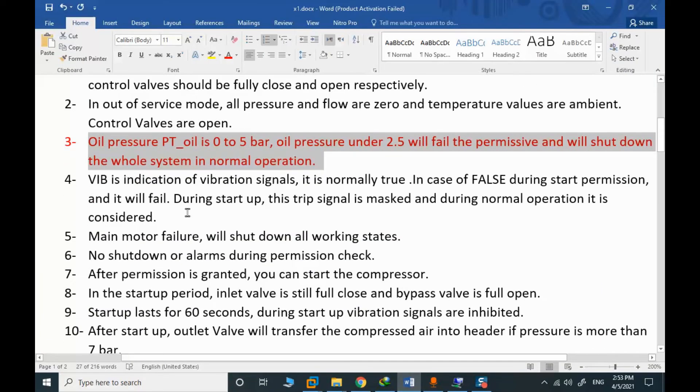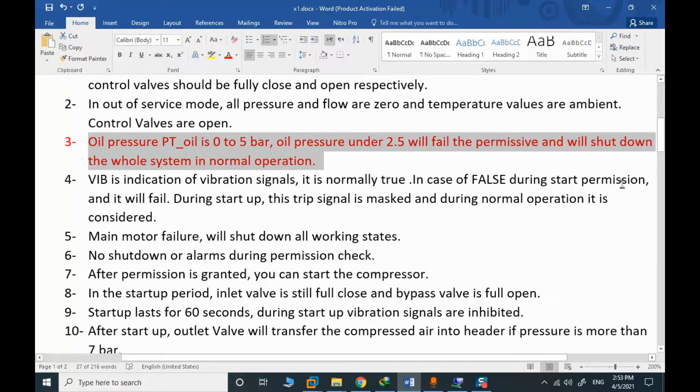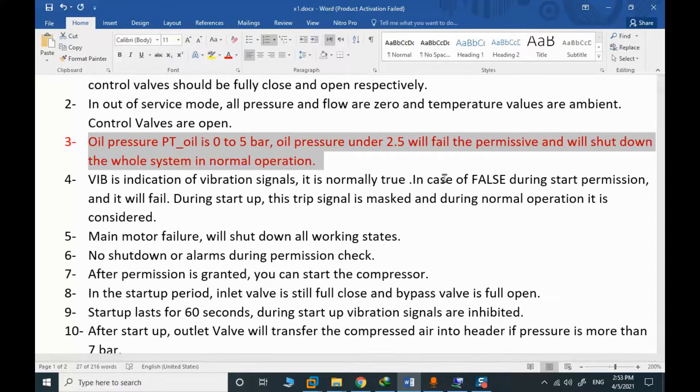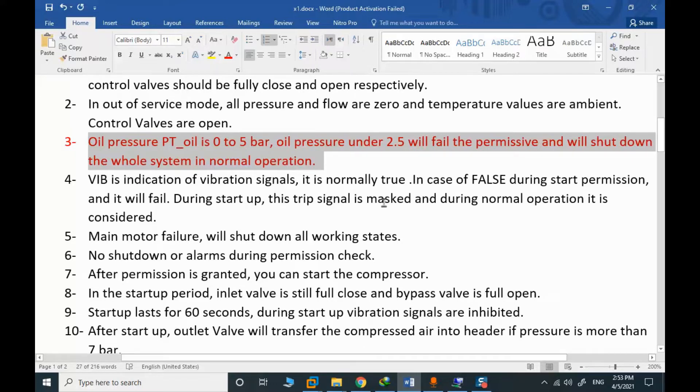Vibration is indication of vibration signal. It's normally true in case of false during start permission. It will fail during a startup. If the vibration switch is false, it means that something is wrong in the vibration system. During the startup, we will inhibit it. It depends on you. You can monitor, it's not a big deal.